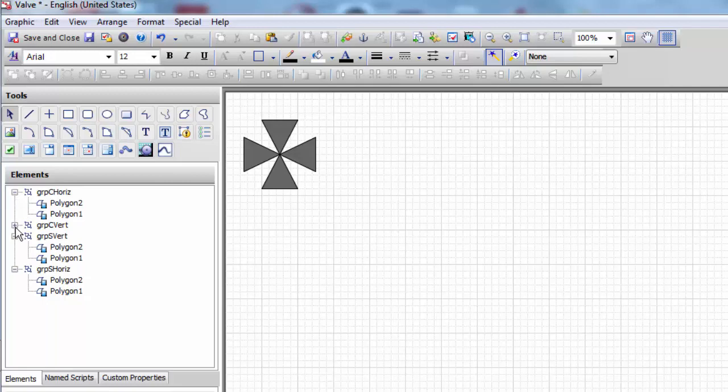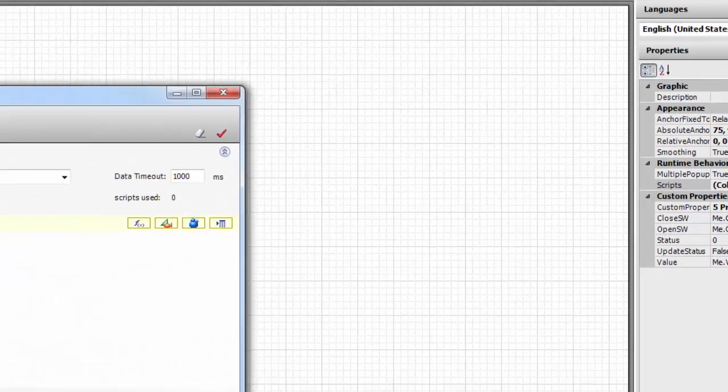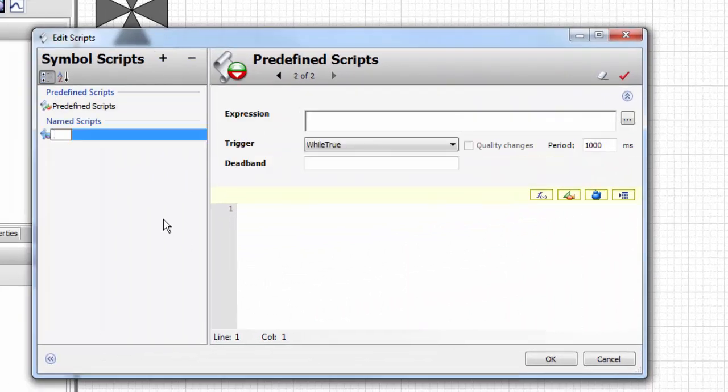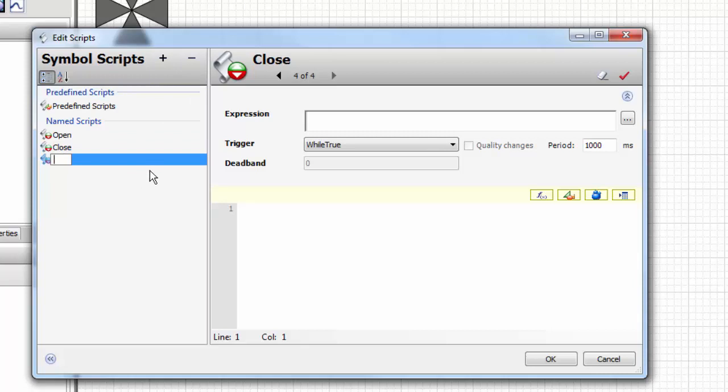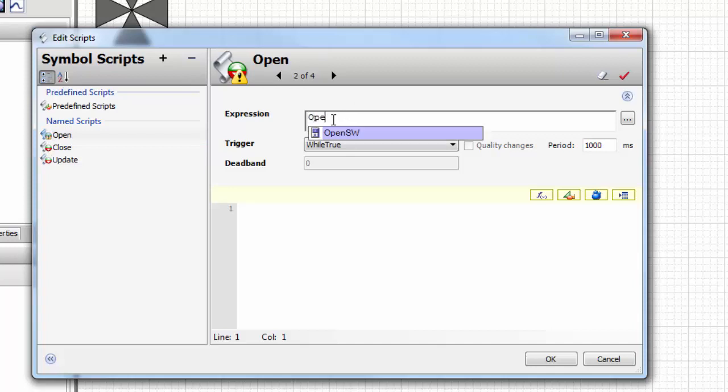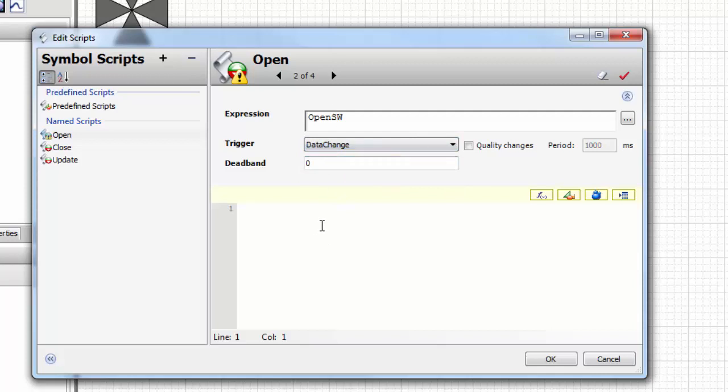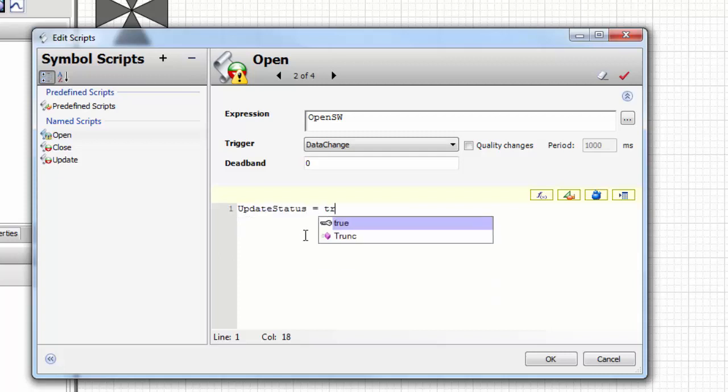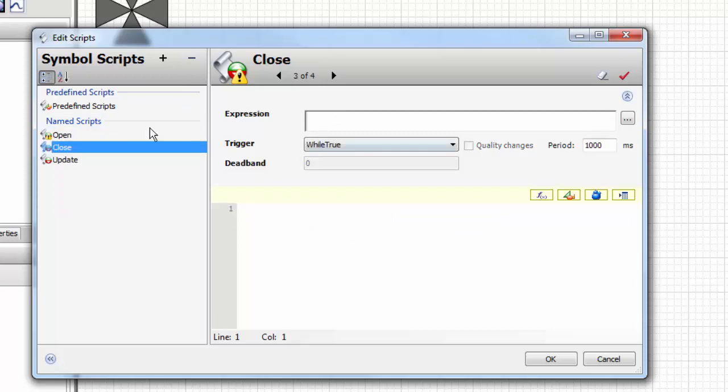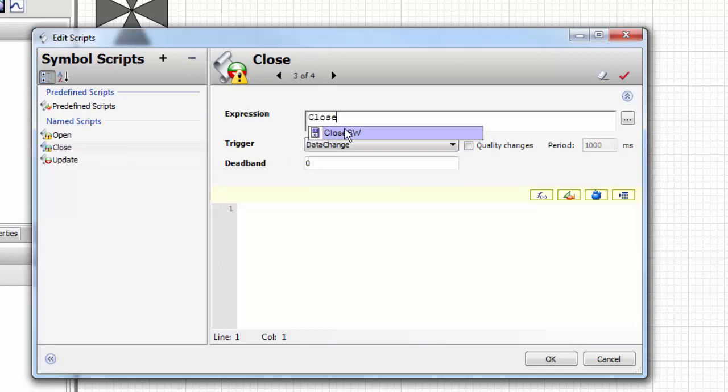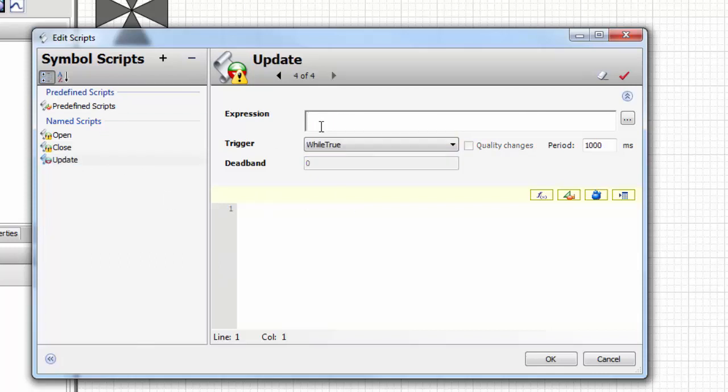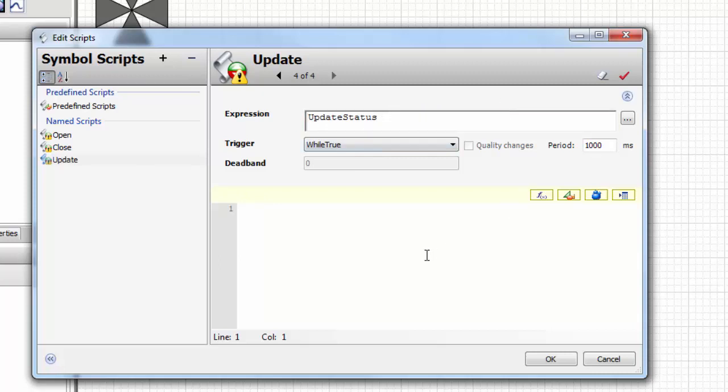Now we're going to create our scripting. The way we're going to maintain this control is we're going to have an open script, close script, and an update script where we'll actually set the status. In the open script we're going to monitor the condition of the open switch, the open input. Anytime it changes, whether it goes true or false, we're going to trigger the update status boolean and make it true. We're going to do that same thing for our closed when it changes.